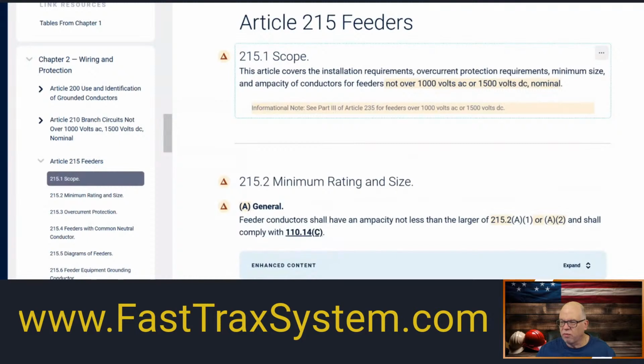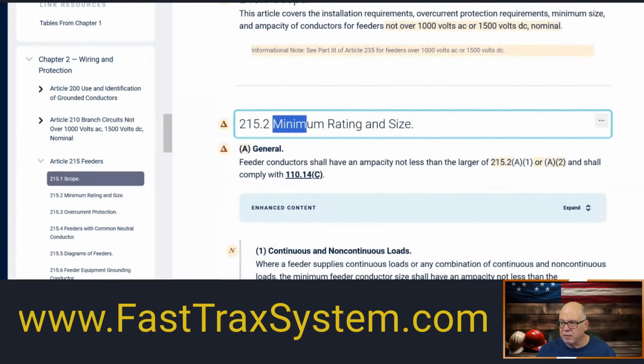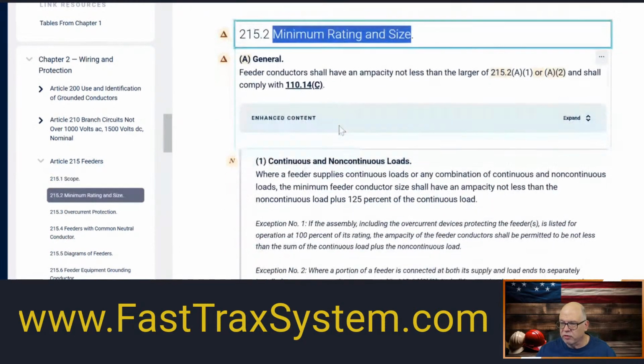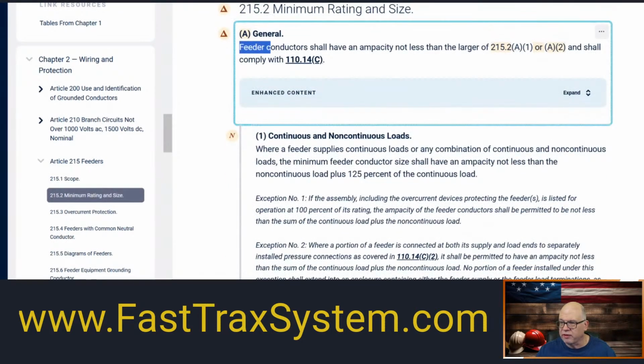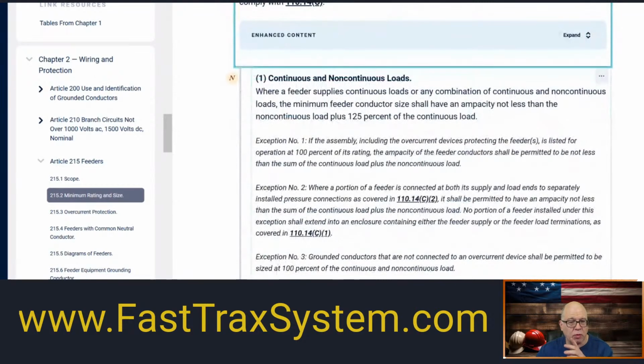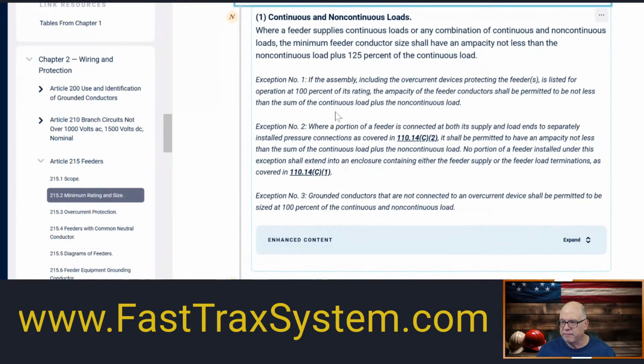Okay, so minimum size. Well, it didn't take us long to get to minimum rating and size for the feeder, all right? So A is general. So the feeder, again, this is very similar to what we saw with 210.19. Very similar. Continuous loads at 125%, non-continuous loads at 100%. That's when you're sizing the hot conductors. So that's pretty straightforward, right?